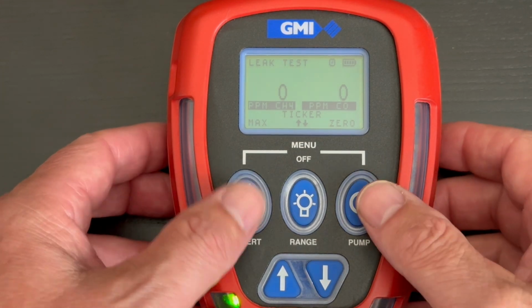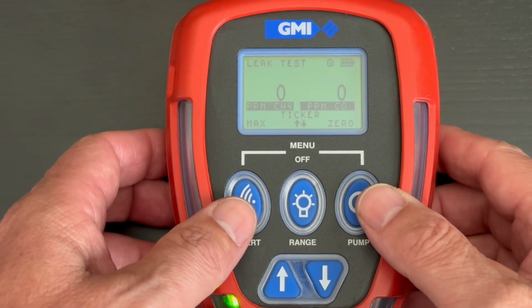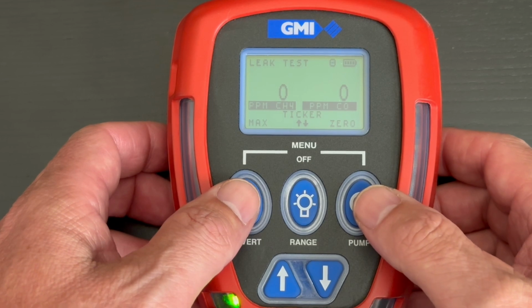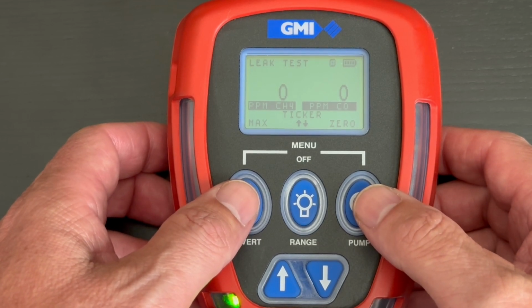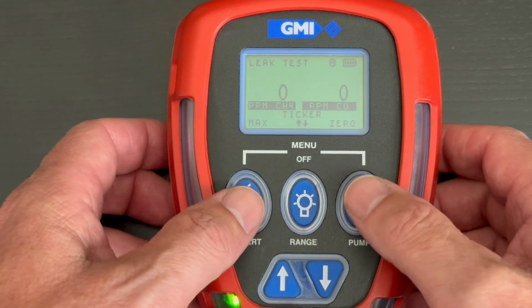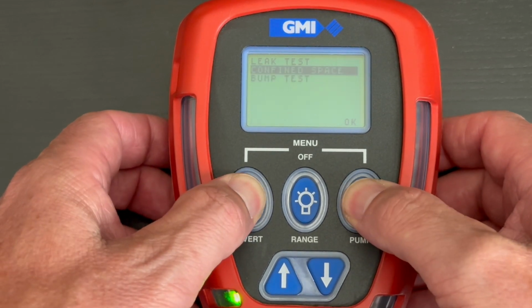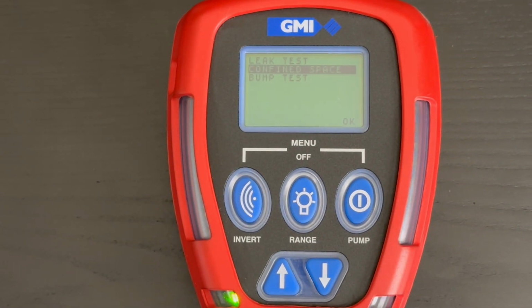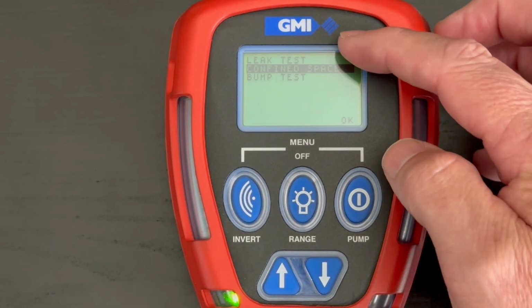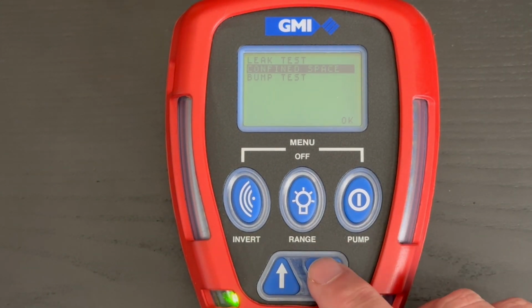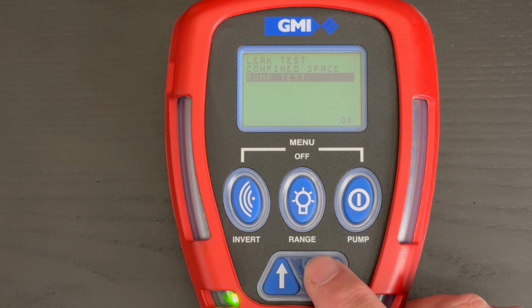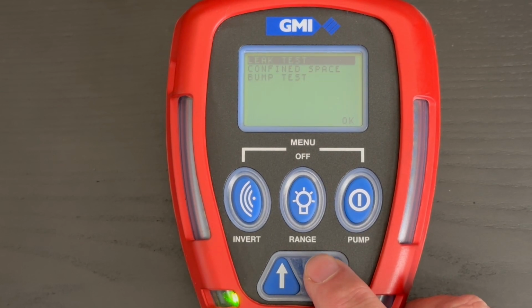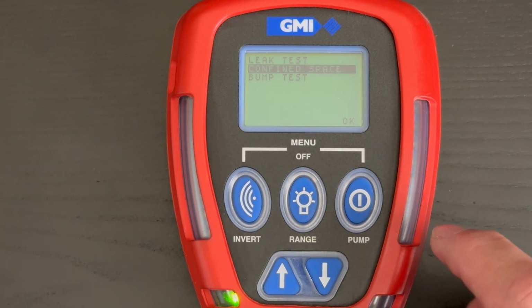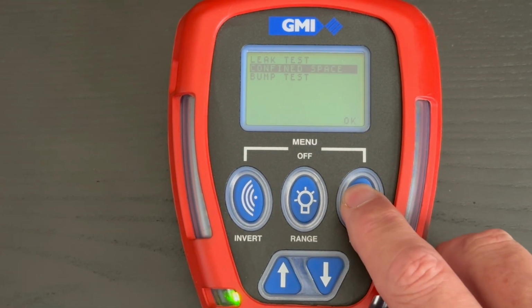To get it out of leak detection mode, if you have confined space sensors inside here, O2, LEL, H2S, and CO, how you get to that is by pressing these two buttons, and you'll notice real quick it moves from leak test down to confined space. What I'm going to do is just use this arrow down and show you how to maneuver those if you wanted to. That'll be important when we get back into leak test. So I'm going to hit confined space mode and hit again the soft arrow key.